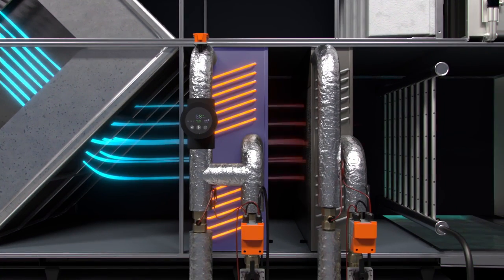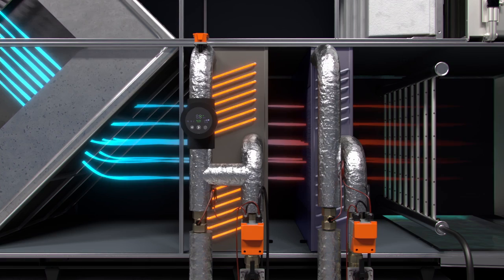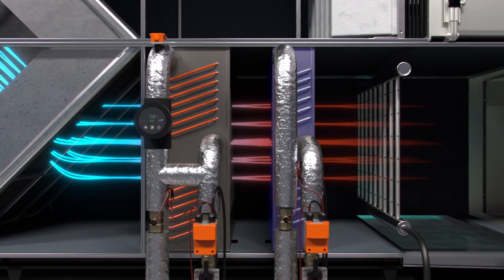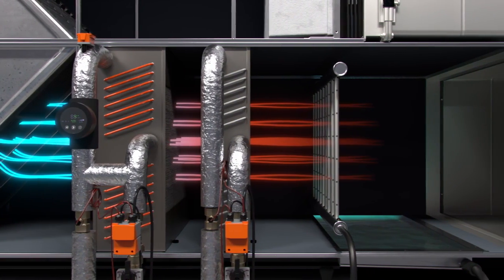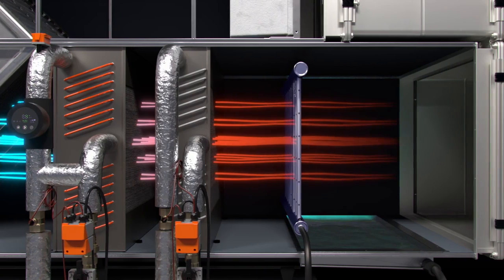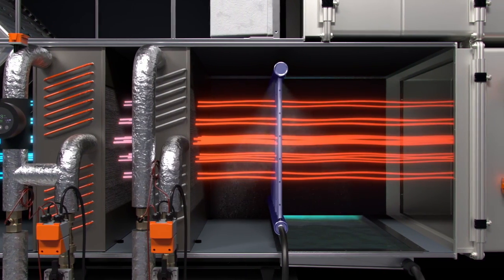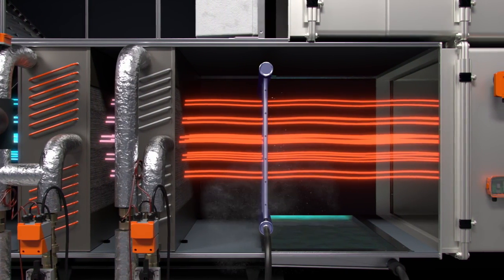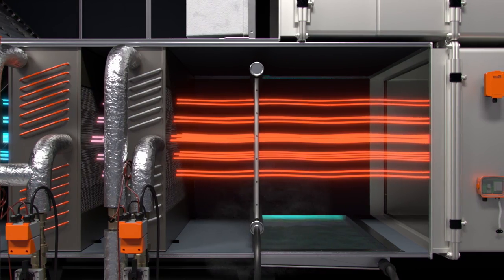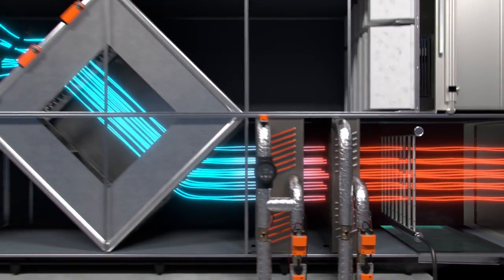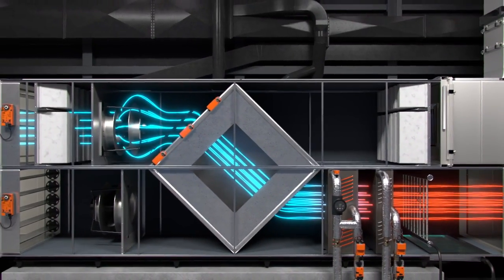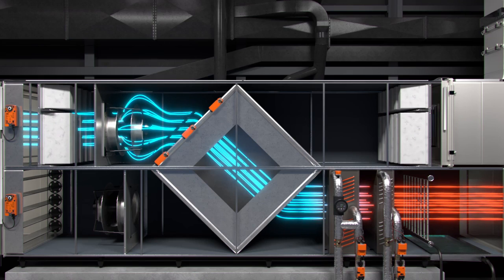In winter, the air is heated in the air heater. In summer, the air could be cooled in the air cooler instead of being heated. Finally, the air is humidified with a steam humidifier if required. The conditioned air is supplied to the rooms and zones according to the demand.